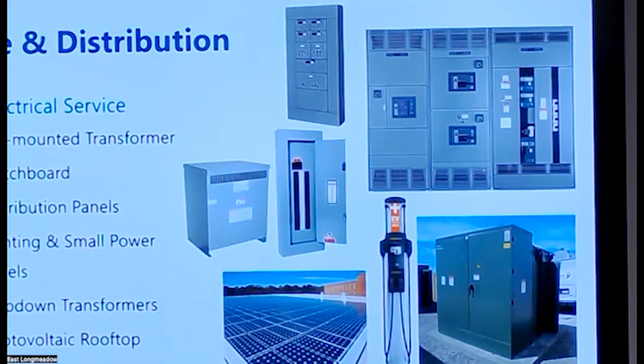And what you see right between the transformer at the bottom and the PV panels in the middle, the bright vertical thing, this is the EV charging station. The one shown here is a dual station, which means two cars can be charging at the same time. Under LEED, we are obligated to provide a minimum of 2% of the total number of spots. But also by stretch code, we need to provide ready spaces up to 10. So we will install 5 dual stations to meet 2%, and then we will provide power for future EV stations for another 8% to make it 10 total.